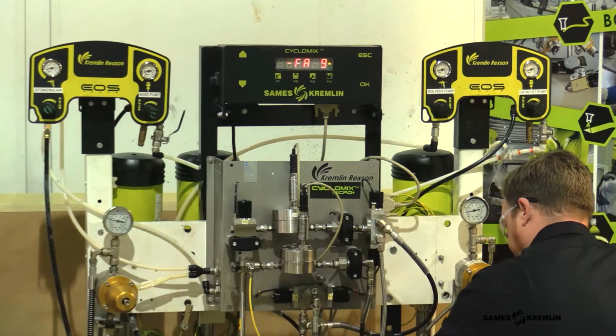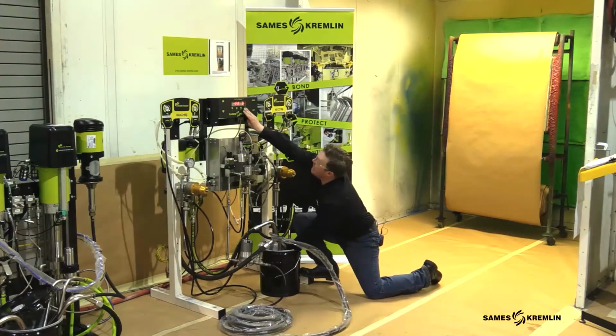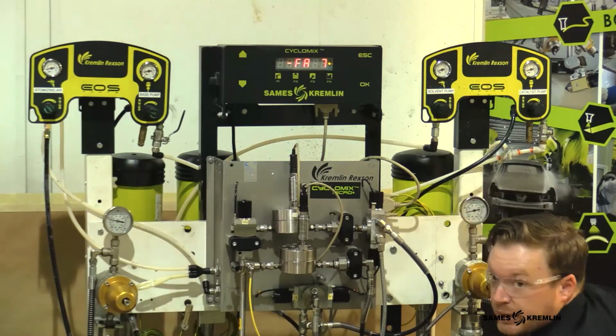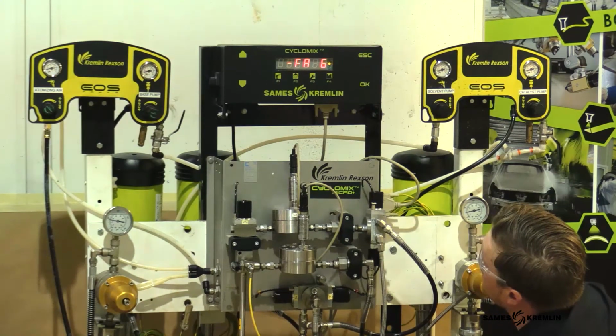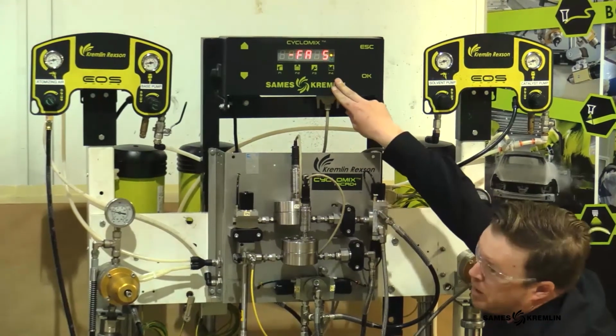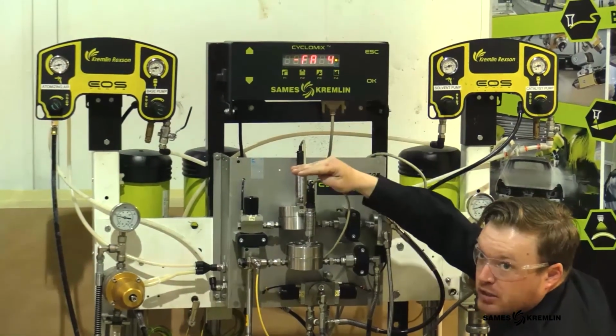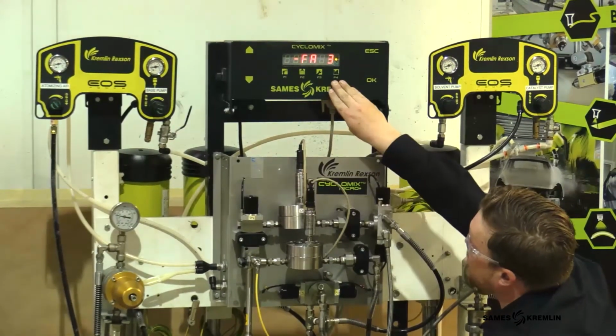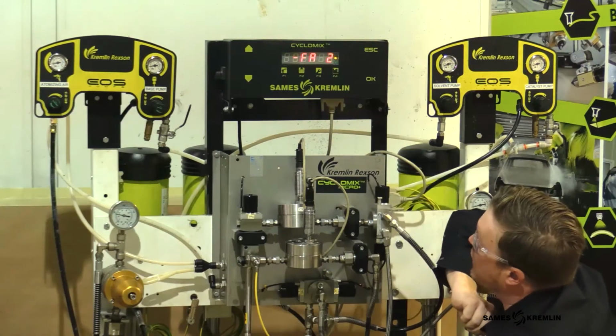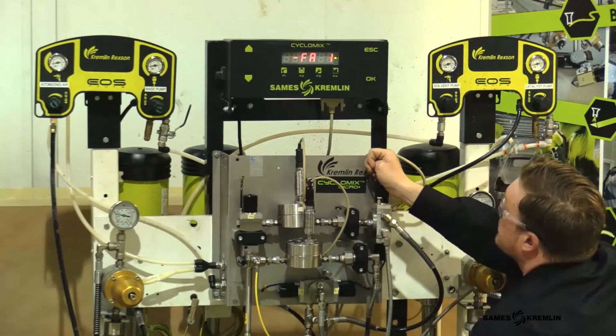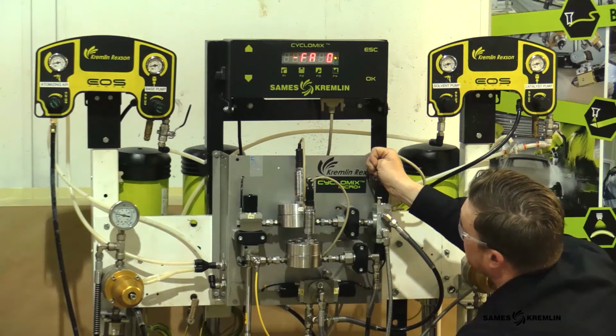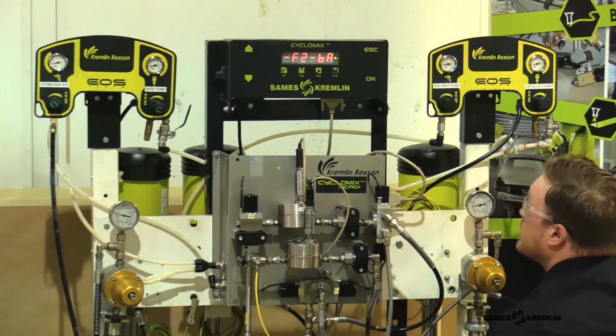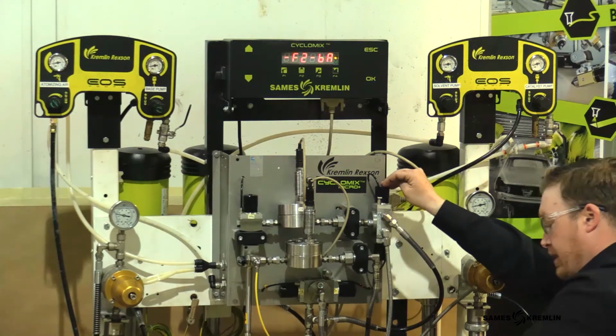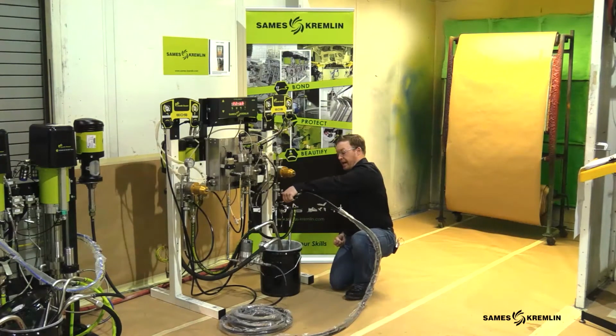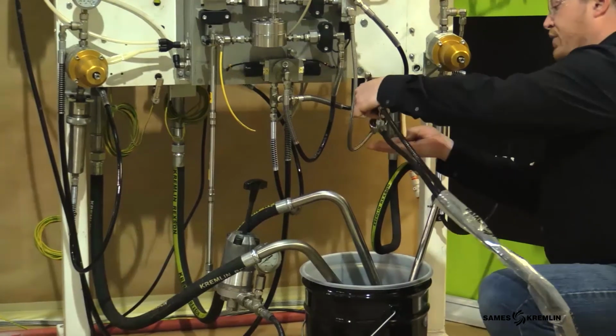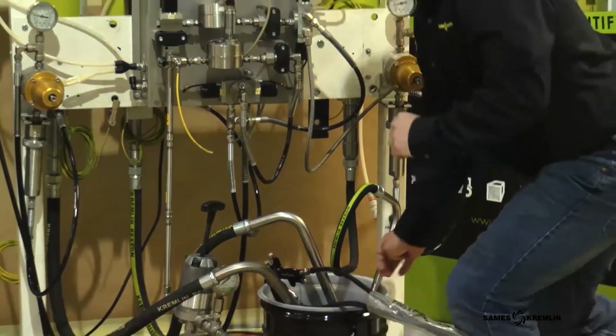Now I'll trigger the gun again, and we'll see it count down, indicating that we are completing the flush. What that value represents is a percentage of the flush completed. So we have 30% left to go, 20% left to go, 10%, under 10%. And from that point, all of the valves turn off automatically, and there is no more pressure out of the gun. It's just dissipating, dissipating, dissipating. As long as everything is good and clear, it's time for your customer to go home.